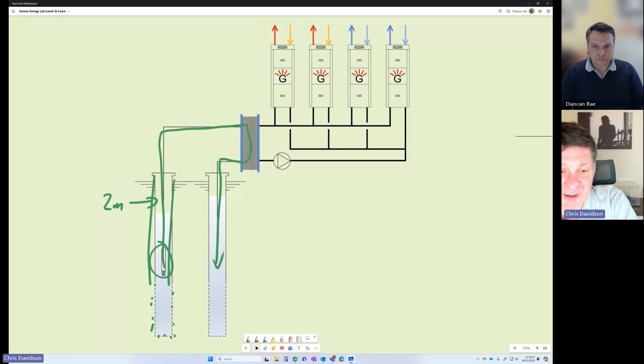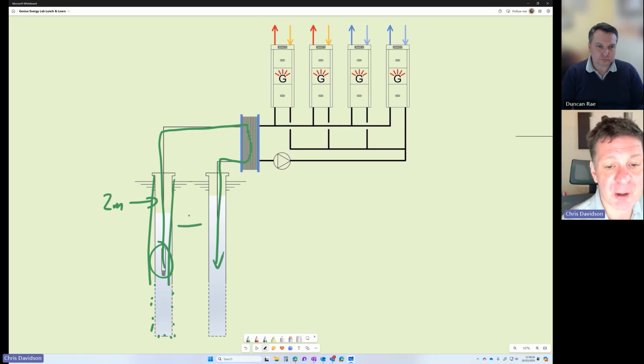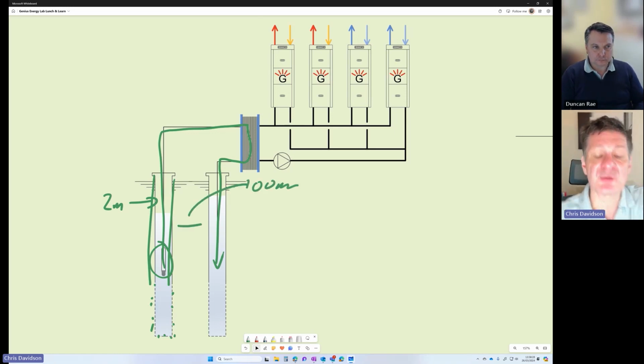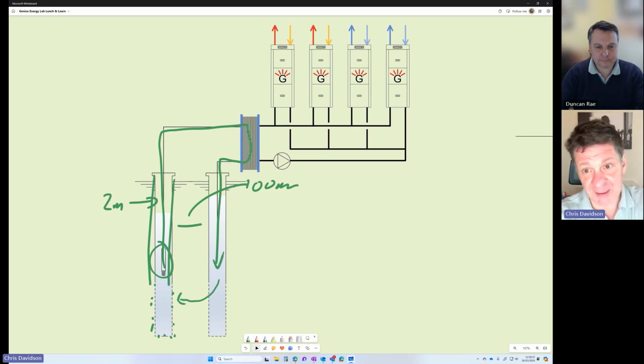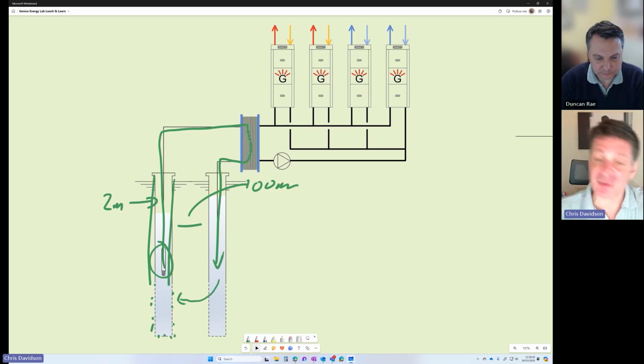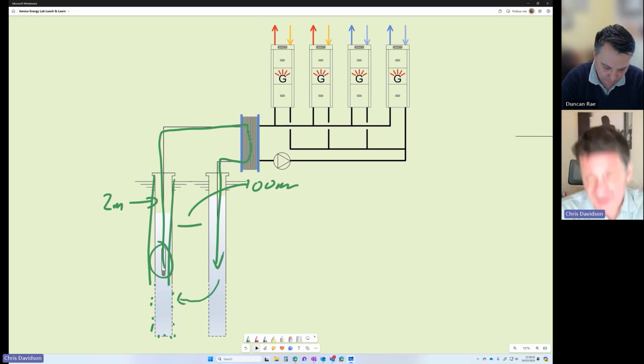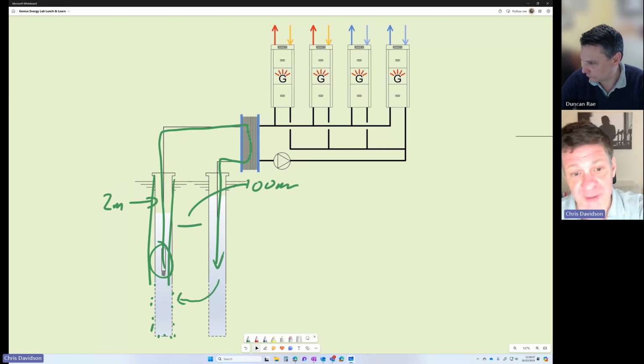Now, for clarity in this drawing, I've drawn the two boreholes very close together. In reality, you need about 100 meter spacing between the two to ensure that you're not getting short cycling, where the water we're putting back into the ground is just immediately heading into and blending with the water coming out of the ground. Imagine you've got a heating-dominated system, that water is going to get colder and colder. It's untreated water, and so it's not got antifreeze in it, so we can't mess around with freezing point, or else we could pop heat exchangers and so on.